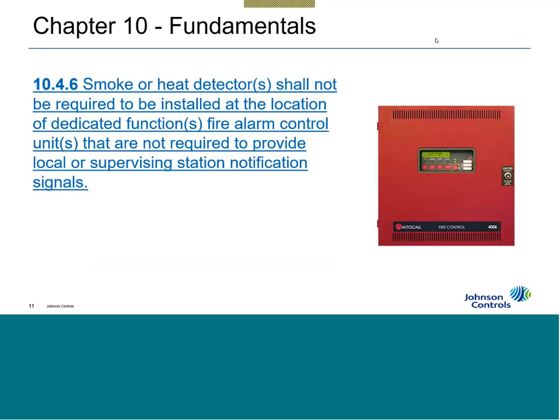And then along with that, again, another thing that you don't have to do, what if I have a dedicated function fire alarm control unit? Do I need a smoke detector above that? Well, let's back up and talk about what a dedicated function system is. This was added a few cycles ago. If I have a two-story parking garage, open air, the building code doesn't require a fire alarm system in that structure. It might have to be sprinklered, but it doesn't have to have a fire alarm. Okay, fine. But it does require, in a two-story building, an elevator. So if I have an elevator, the smoke detectors need to tie to the fire alarm control unit. I don't have a fire alarm control unit, so what do I do?